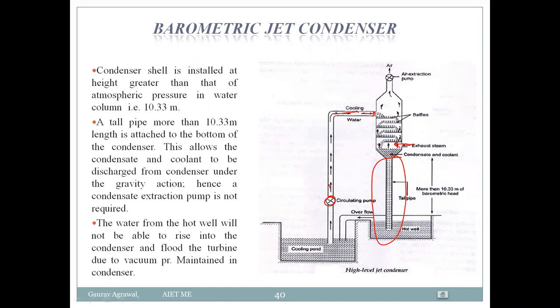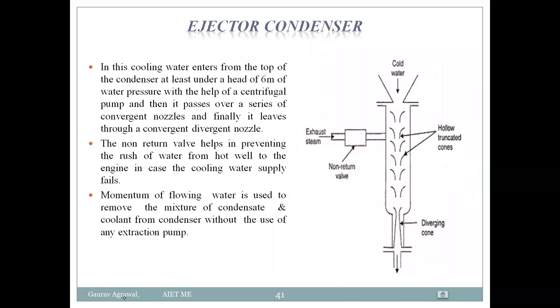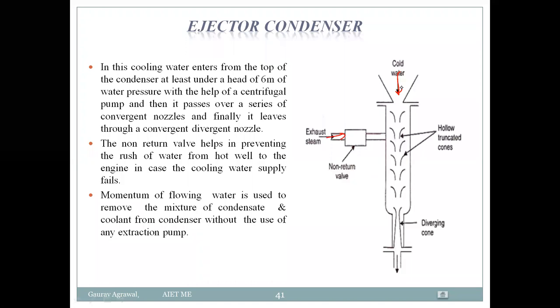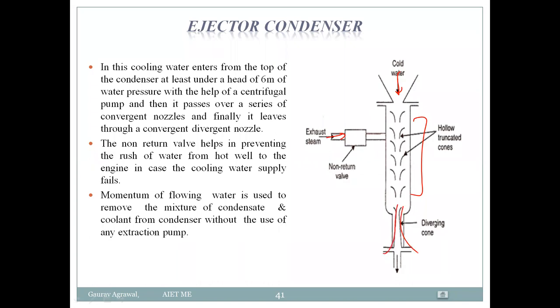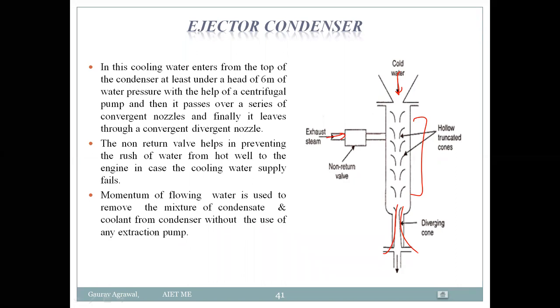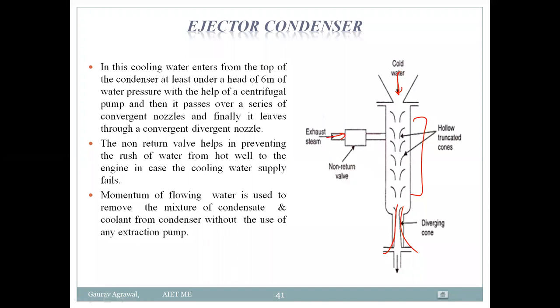Next is the ejector condenser. In this type, nozzles are used. Cold water and exhaust steam both enter the system, passing through a convergent nozzle followed by a divergent nozzle. A non-return valve is used so that water from the hot well does not rush back to the engine if the cooling water supply fails. The momentum of the flowing water is used to remove the mixture of condensate and cooling water from the condenser without an extraction pump.